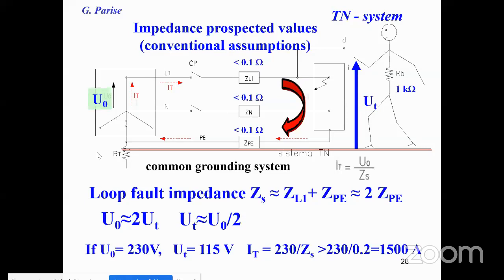And so, considering the same reference values for a low voltage circuit in fault condition, we have a value of lower than 0.1 ohm for the line and the same value for the protective conductor. If we assume 200 volts of line-to-earth voltage, the touch voltage assumes half that value. So if I have 200 volts, the touch voltage can be conventionally assumed to be half, 100 volts.